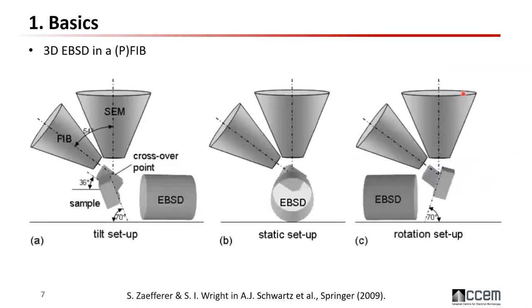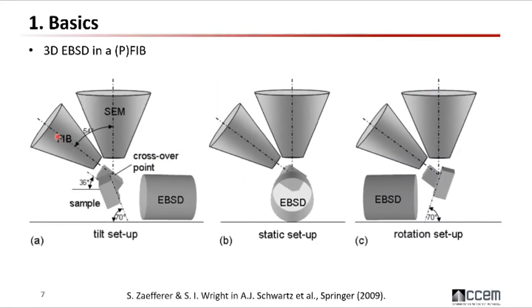3D EBSD in the FIB has been developed for a long time — the first paper, if I remember, was published in 2004. Here is an illustration of how different configurations work with respect to the relative position between your FIB column and the EBSD camera. You have three configurations. In the tilt setup, you have one cross section parallel to the milling position and another cross section tilted to 70 degrees for EBSD. For the tilt setup, you tilt between these two positions and may need to adjust X and Y to keep your region of interest in view.